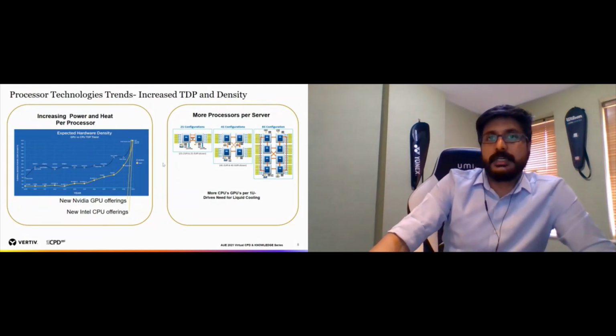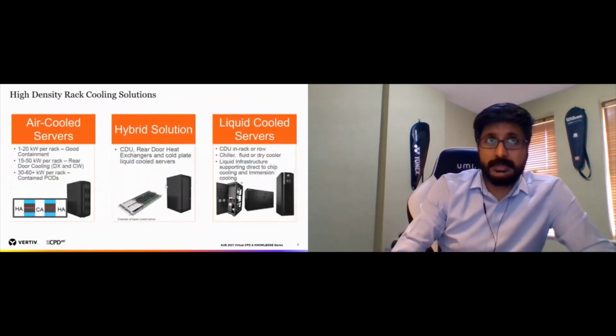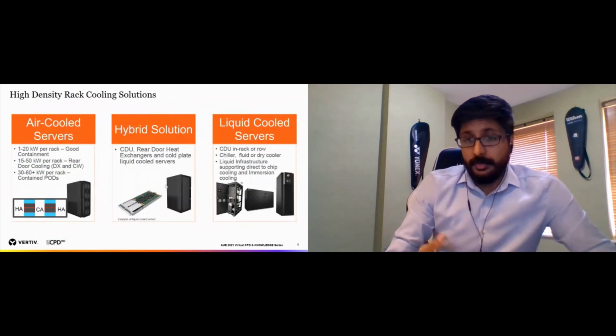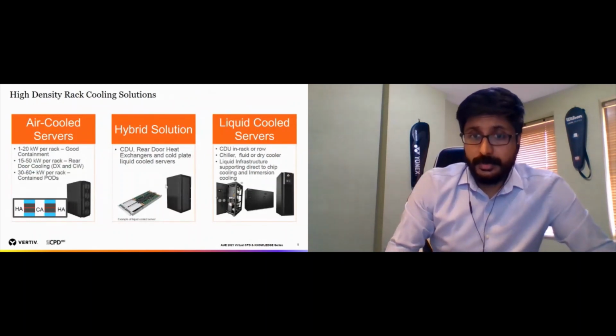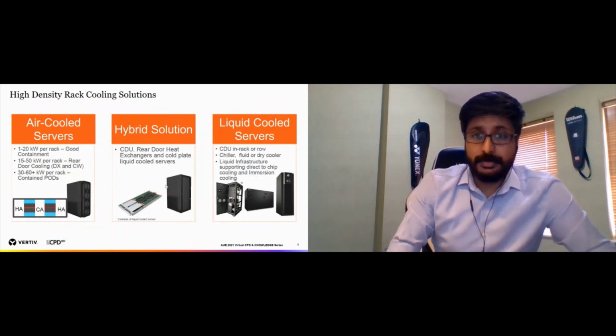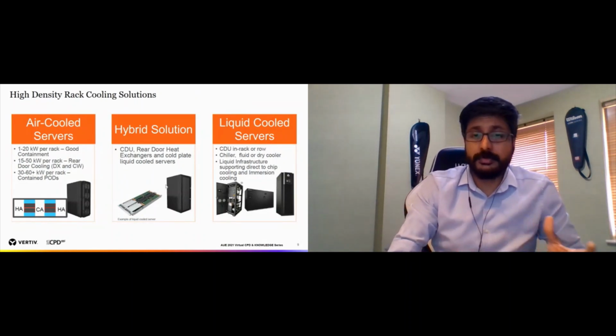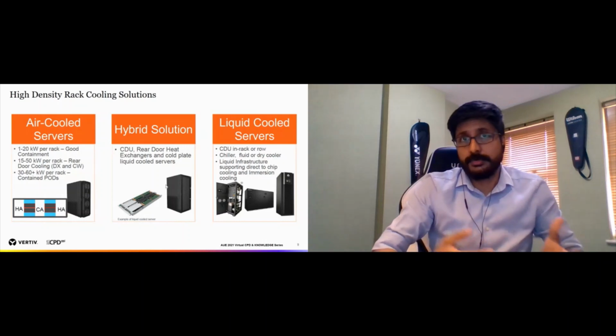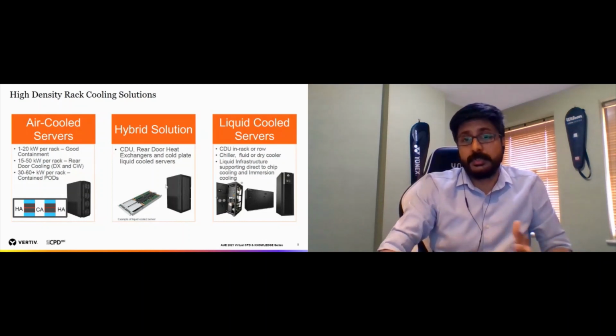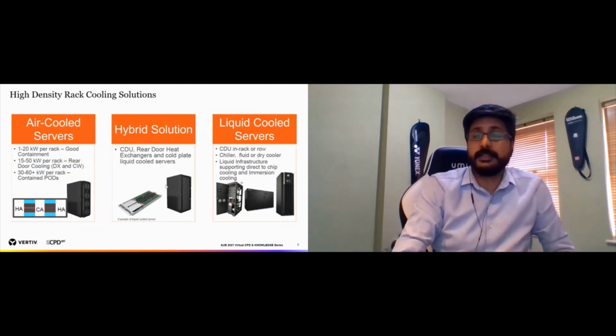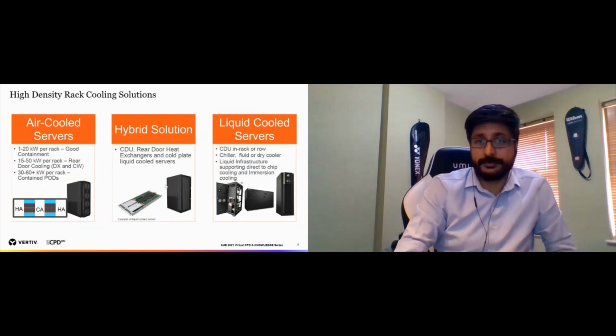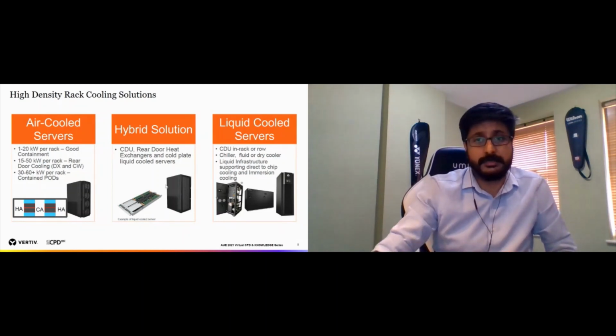And that's where the high density cooling solutions come in, and the different options that we can have is we can go for air cooling, which will be the rear door cooling solutions. And then we can have a hybrid solution where there's a combination of the rear door cooling, air cooling solutions and also liquid cooling. And then you can have fully liquid cooled servers as well. So those are 3 different options that we can currently have for high density rack cooling solutions.